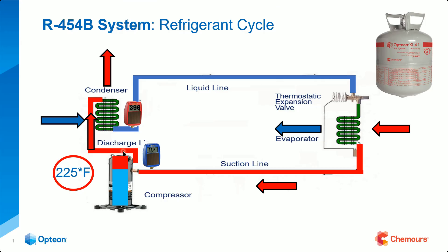Six inches out — the reason for that is engineers and scientists figured out that we lose somewhere between 50 to 75 degrees Fahrenheit of temperature from the hottest point of any compressor. It's not brand-specific, not based on refrigerant — it's really based on oil. So if you take the worst scenario of 75 degrees and add that to 225, you get the magical number of 300 degrees Fahrenheit. At 300 degrees, we start to lose lubricity. When we lose lubricity, we start to cause friction in the compressor. The number one cause of compressor failure is overheat.